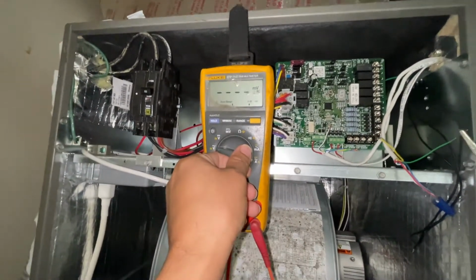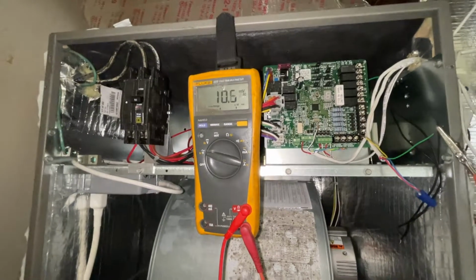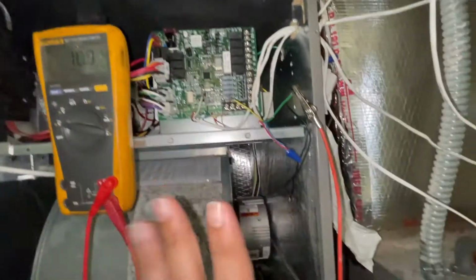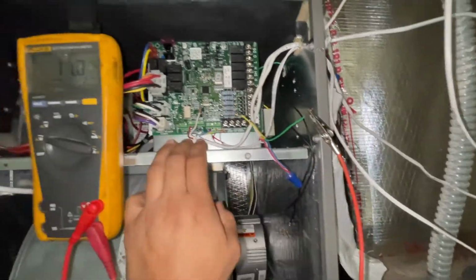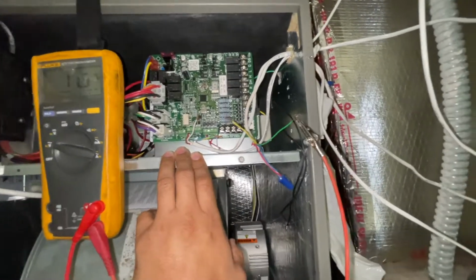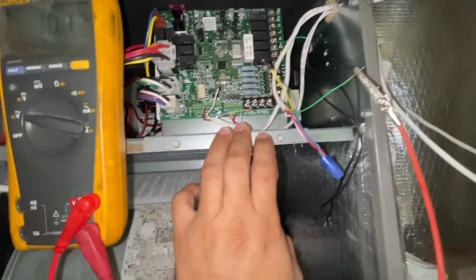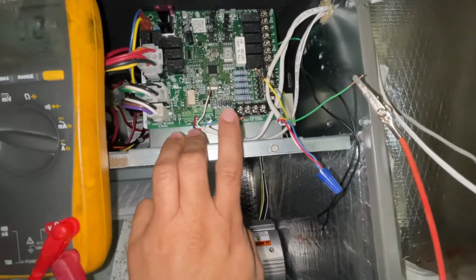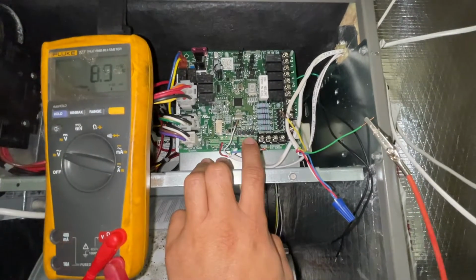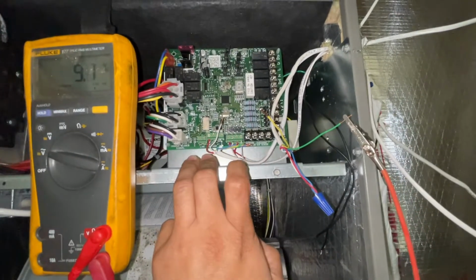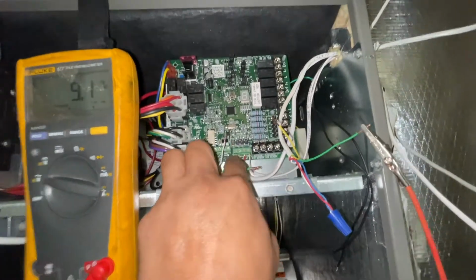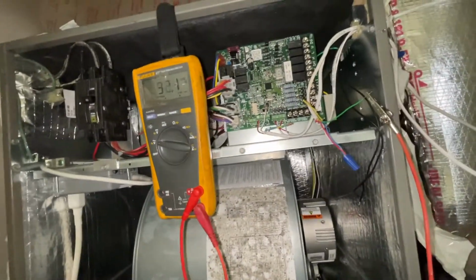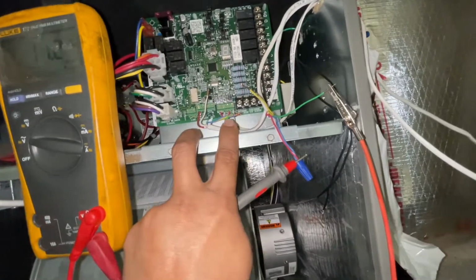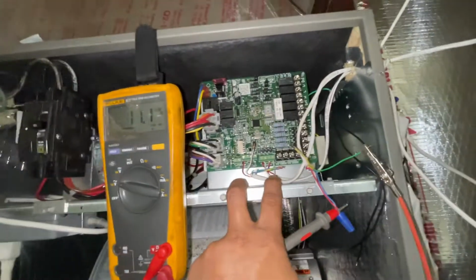Let me show you a way you can test it. Put your meter on AC. Before you do any kind of setup, you want to make sure everything is isolated and turned off. In my case, this is a spare wire that is going to the outdoor unit. Since I was getting a lot of transient voltage on these two wires, I lifted them and measured the AC from my reference to common. So you can take one lead and reference it to common, and then put the other lead of your meter to one of these wires and see what your voltage is like. In my case, the voltage on this wire was a lot higher, about 20 to 30 volts AC, which is not correct.